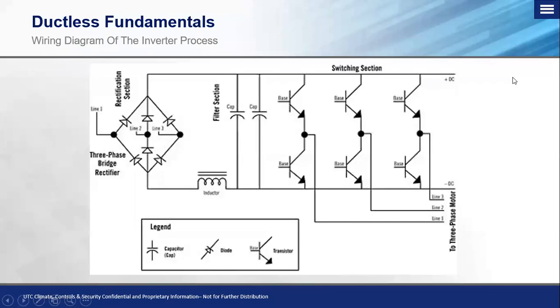So here's the trick question, and where everybody kind of gets goofed up with this. Are these inverter compressors AC voltage or DC voltage? Most of you would probably answer DC, because a lot of you see the DC on the side of the compressor. And that's not correct. What those compressors are with that DC marking on them is digitally commutated, not direct current. Those are actually AC compressors.